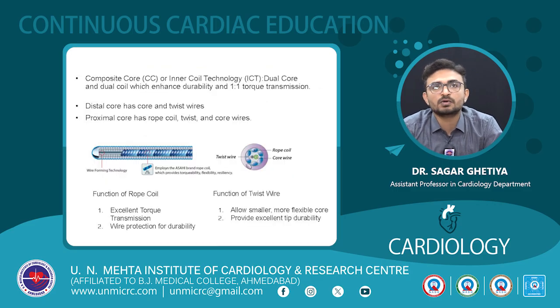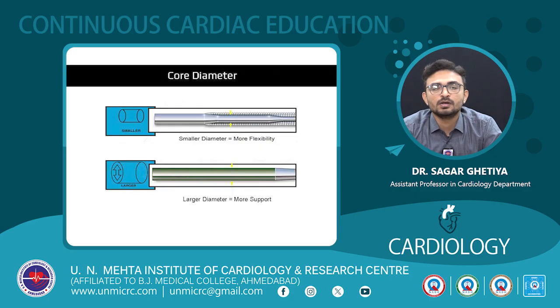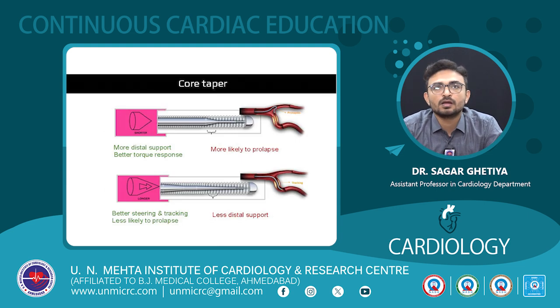Another technology has come, composite core technology, employed by the Asahi brand, which uses rope coil and twisted wire to provide good support and better flexibility. Another component is core diameter. A smaller core diameter means more flexibility, while a larger diameter means more support. Another is core tapering. A shorter core taper provides more distal support and better torque response, but it comes at the cost of an increased chance of prolapse.